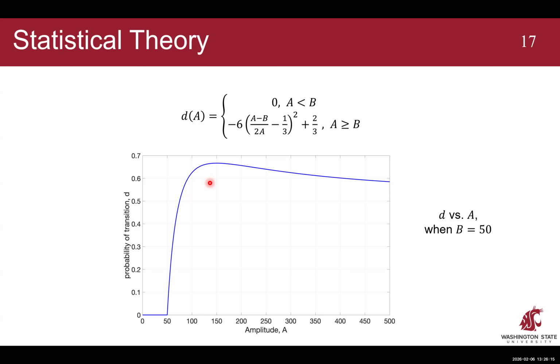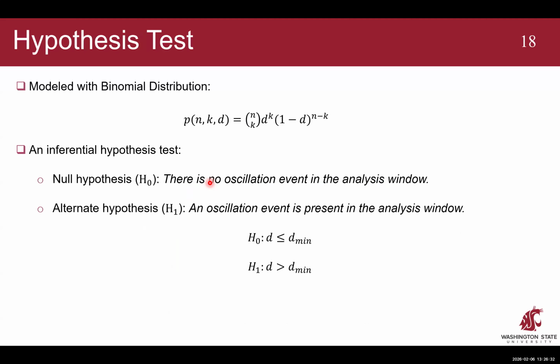And we can again make this rigorous because we have these individual observations. Each of them, either there is a transition or there is no transition. So it's a simple Bernoulli distribution. Then if I count the number over n experiments, the total number will be a binomial distribution. And since in SCADA measurements there is no correlation between when consecutive samples occur, because of the asynchronous polling used in SCADA architecture, we can show that the consecutive observations will be independent. And this helps formulate this problem nicely as a binomial distribution.